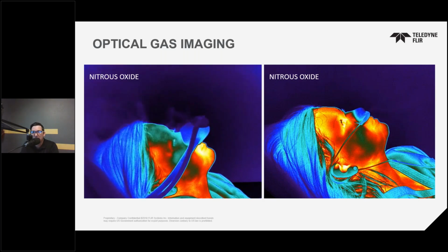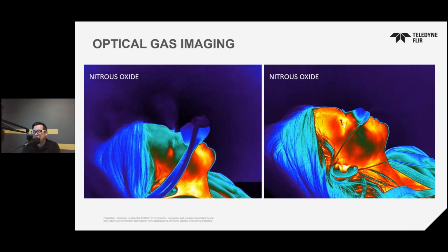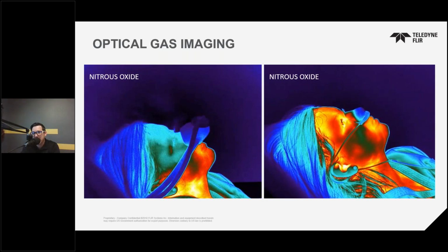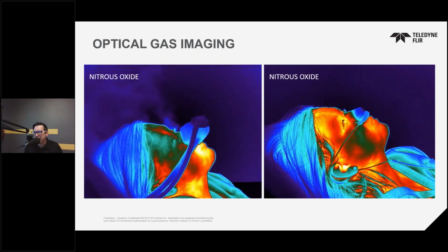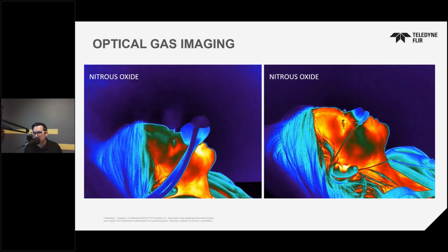In this example, the product designer was doing some R&D testing on a new mask for administering nitrous oxide to patients. There had actually been some complaints from the dentists, doctors, and nurses that they might be feeling the effects of the gas, which none of you want, to have them loopy on inhalants while working on you. In the video on the left, you see the original design, and as expected from the feedback, there is a lot of leakage occurring. Not only is this dangerous for the medical staff working on you, but it makes it challenging to know the dose that the patient is actually receiving, and not getting enough nitrous before surgery is also very terrifying from my perspective.